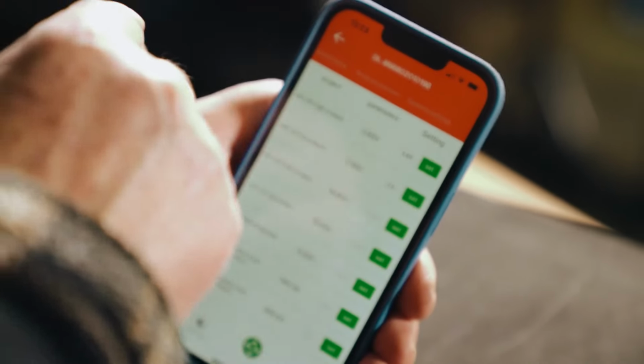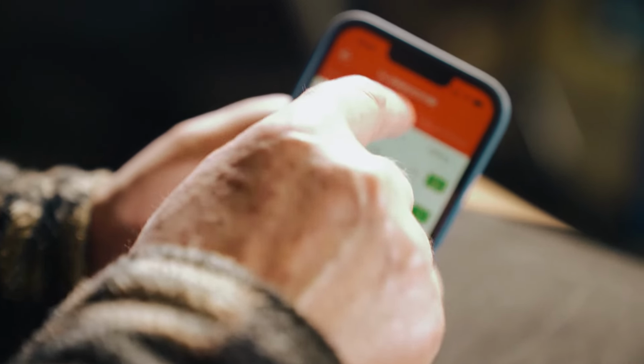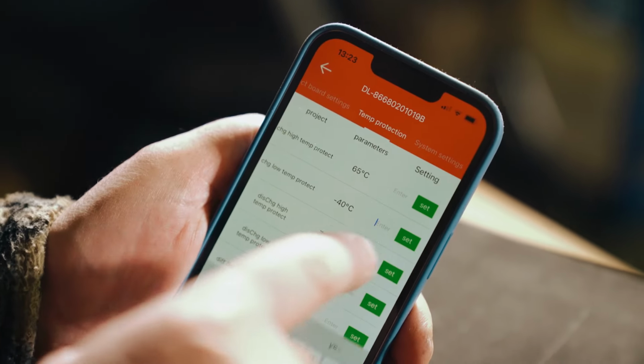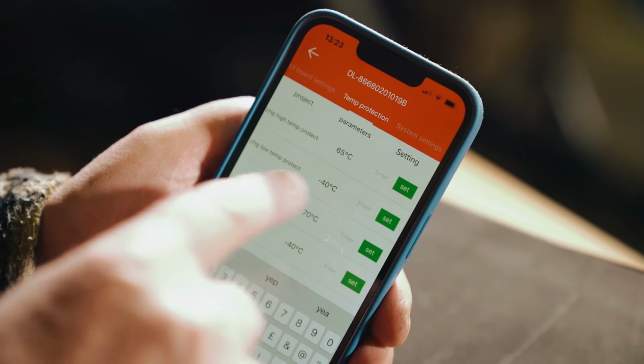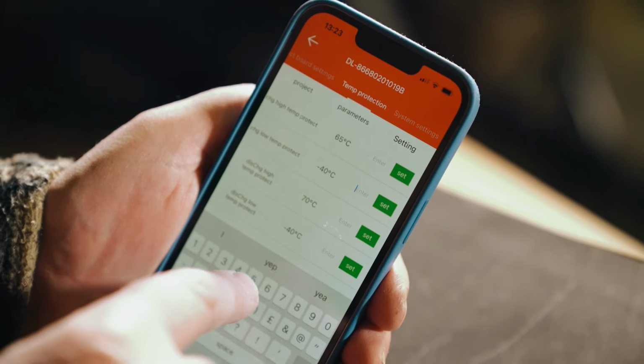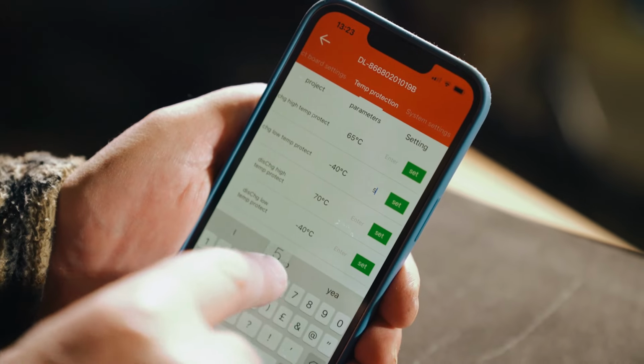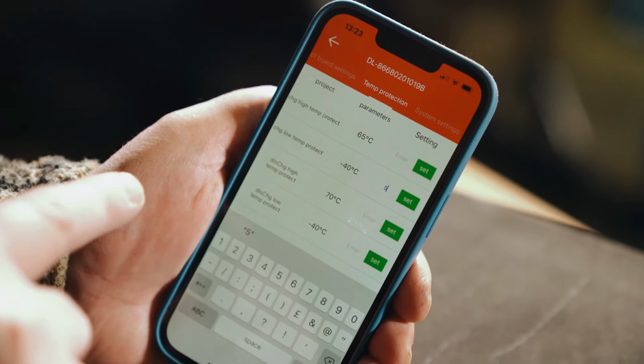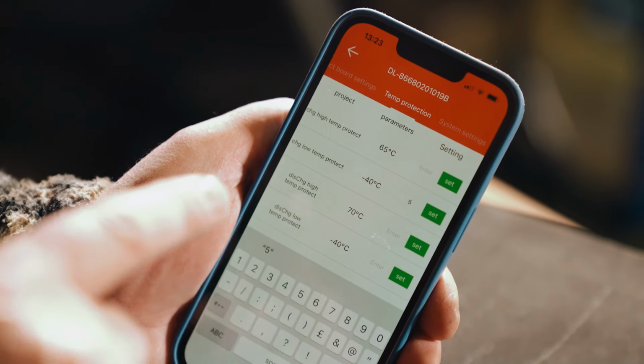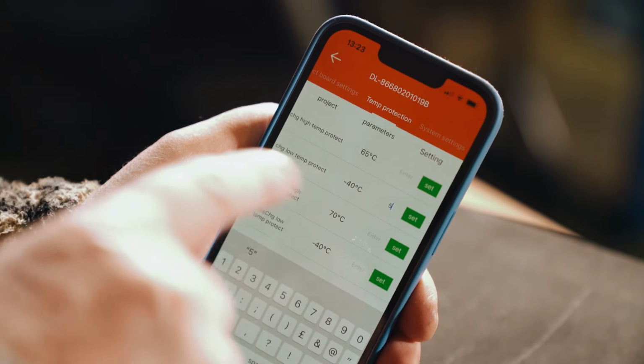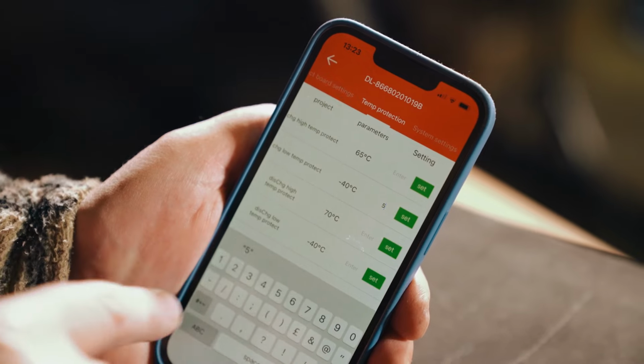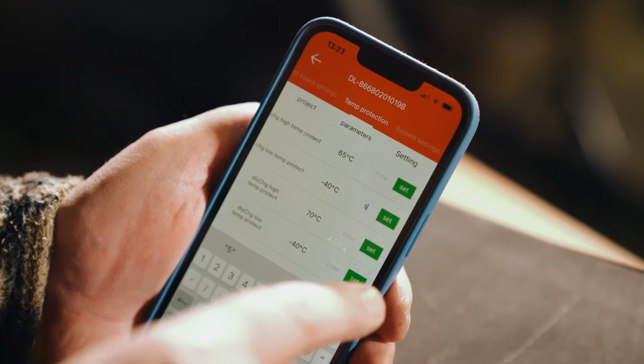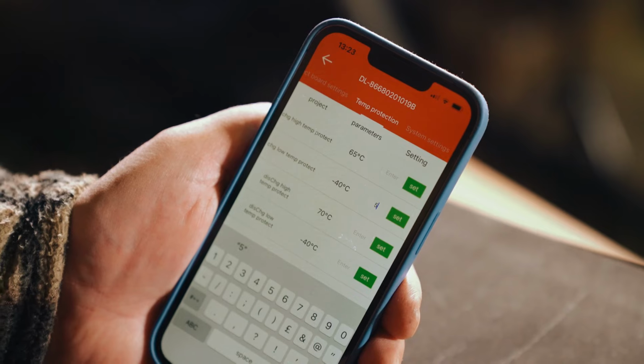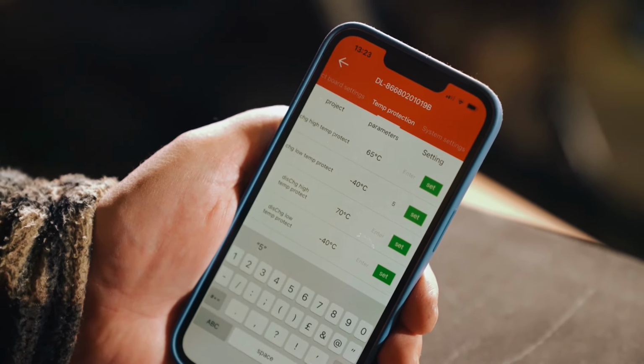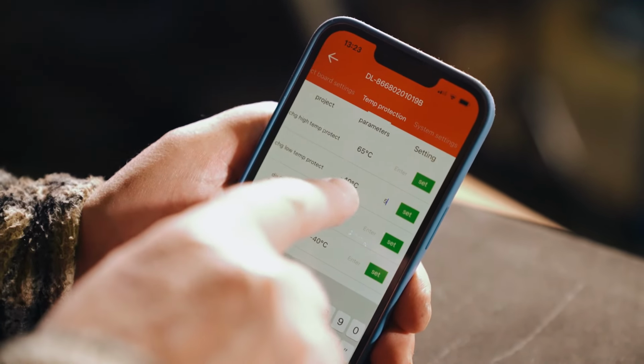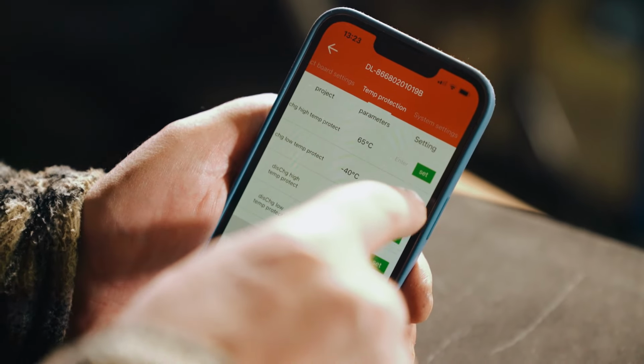We swing across here to temp protection, which starts off at a crazy minus 40. That's going to damage the cells completely. We change ours to anywhere between 3 and 5. Generally these are on the side of caution, so when it's actually 5 degrees, the BMS will show 3 degrees, usually 3 or 4 degrees. So it underreads by about 1 or 2 degrees centigrade.